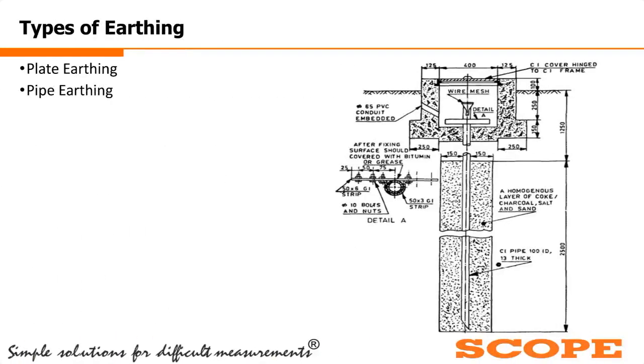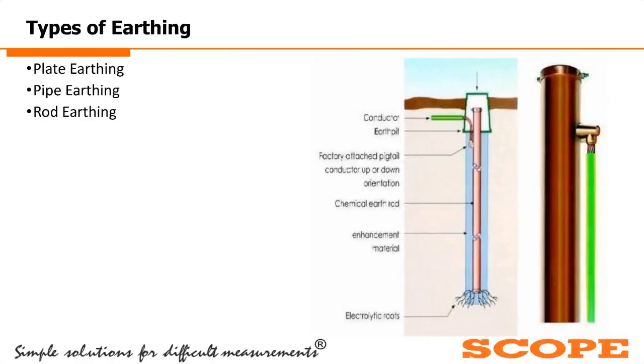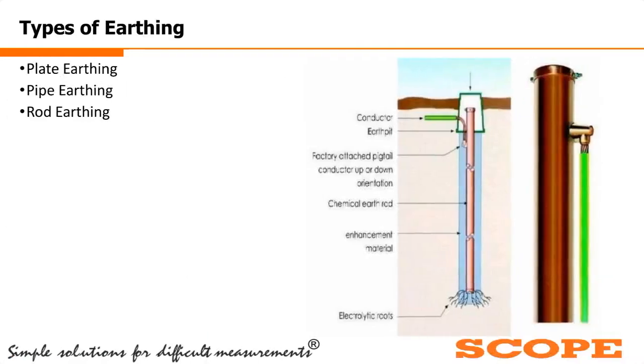Next is pipe earthing. Instead of copper plates, generally hollow pipes are used in this type of earthing. And if we use solid rods, then that type of earthing is called rod type earthing.